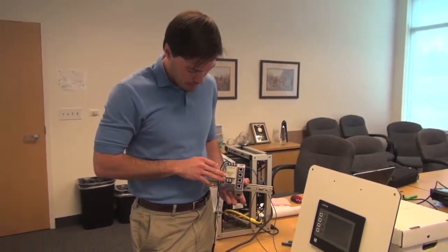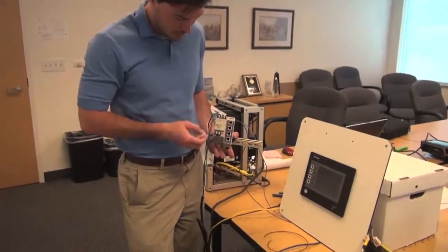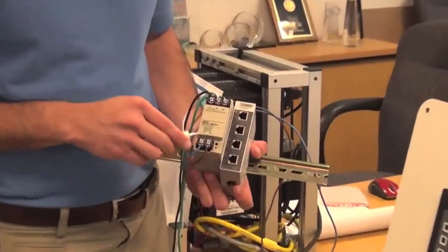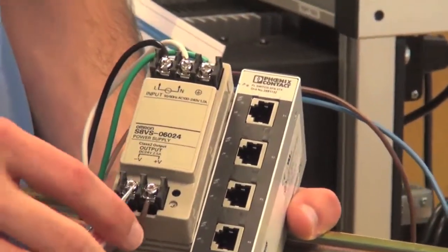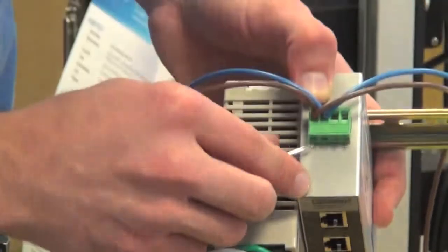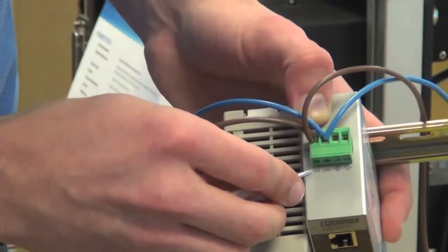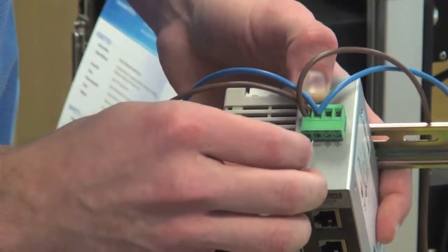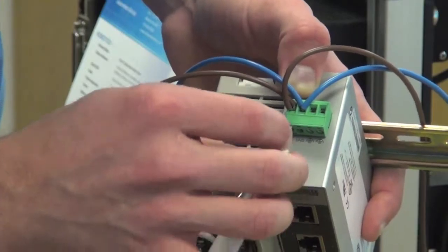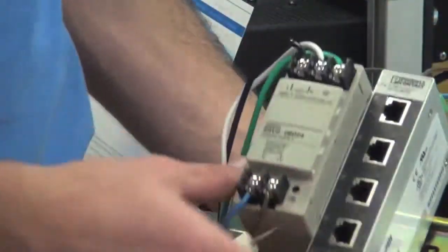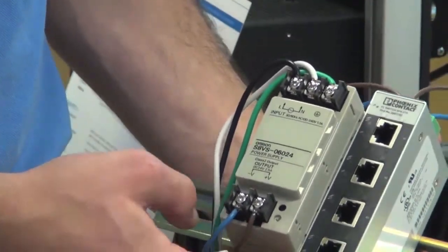Here is the output of the 24 volts DC power supply hooked up brown to your positive voltage lead and blue to your negative voltage lead, connecting them on the ethernet switch. Brown going to the US pin and blue going to your GND ground pin. Your ethernet switch is now powered up.